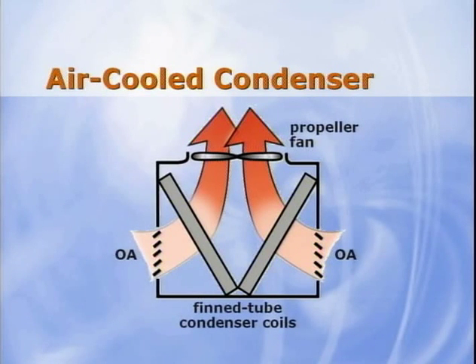The temperature difference between the hot refrigerant vapor flowing through the heat exchanger and the cooler dry bulb temperature of the outdoor air induces heat transfer, causing the refrigerant vapor to condense into a liquid. Air-cooled condensers are very popular because of their simplicity and convenience, and they're widely accepted as the most effective first-cost solution. Outside of an occasional cleaning, the air-cooled condenser requires very little maintenance. Evaporative cooled condensers are specified in far fewer packaged rooftop applications.